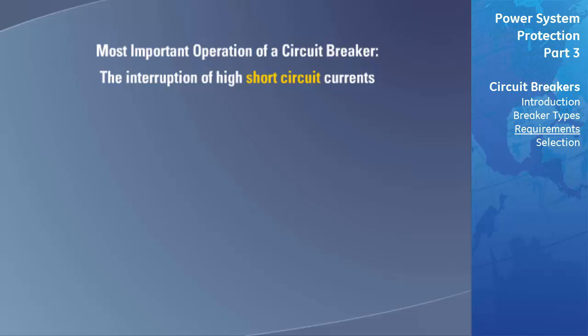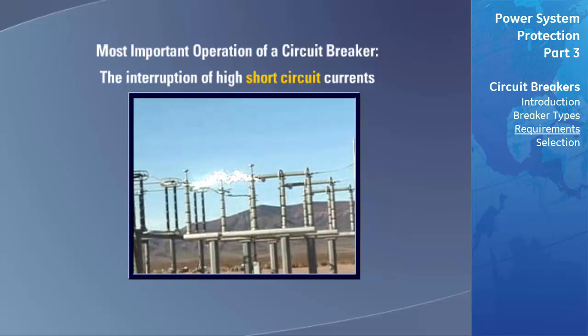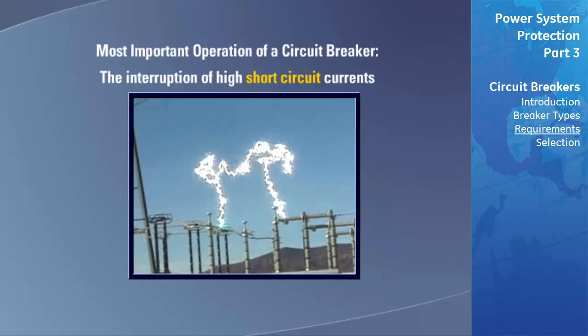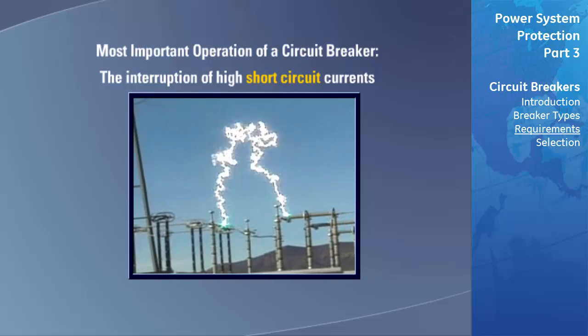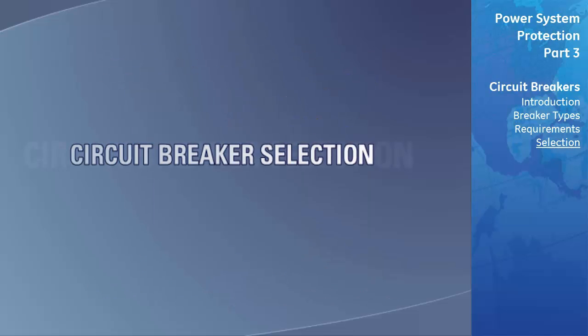The most important operation of a circuit breaker from the protection aspect is the interruption of high short-circuit currents. The energy dissipated during breaker operation is extremely high. For example, the energy dissipated per phase by a three-cycle breaker interrupting 10 kiloamps of short-circuit current is almost equivalent to stopping 100,000 kilograms moving at 36 kilometers per hour in approximately 50 milliseconds.